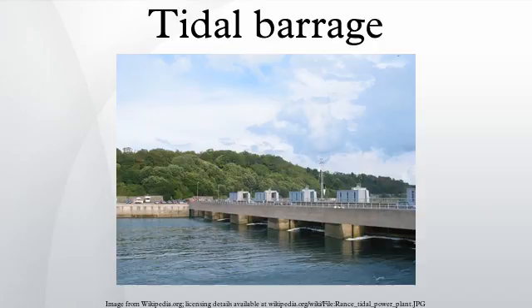Tidal lagoons are independent enclosing barrages built on high-level tidal estuary land that trap the high water and release it to generate power, around 3.3 watts per square meter. Two lagoons operating at different time intervals can guarantee continuous power output, around 4.5 watts per square meter. Enhanced pumped storage tidal series of lagoons raises the water level higher than the high tide and uses intermittent renewables for pumping, around 7.5 watts per square meter — a 10 km² lagoon delivers 75 MW constant output 24/7. These independent barrages do not block the flow of the river.